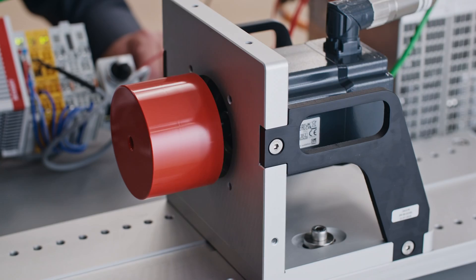And so what we found out now when we hook up the mechanics in the system is that we're working with a 27 to 1 inertia mismatch.